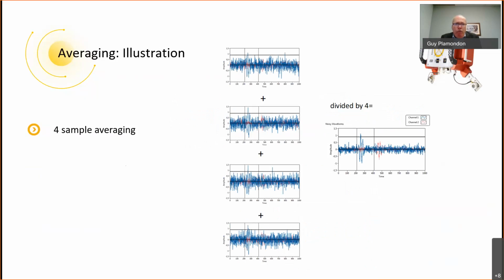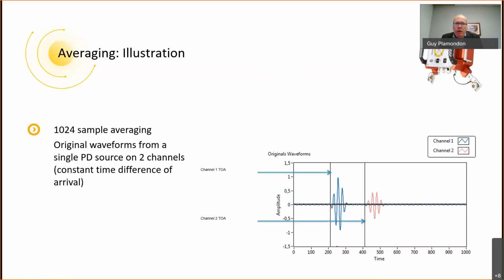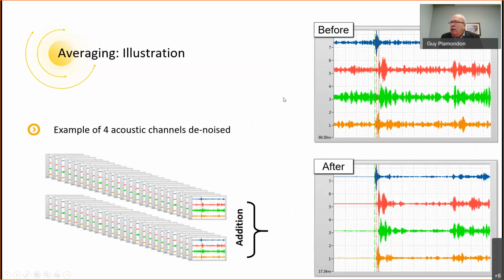So here, after only 4 acquisitions, we can already see on the right the noise disappearing, and we can get out of the noise the acoustic signal we're looking for. The end result, after 1,024 acquisitions, we can clearly see the original waveform of the PD signal itself. Then a real case here, our 4 acoustic sensors, signal before and after. You can clearly see the way we successfully denoise those signals.